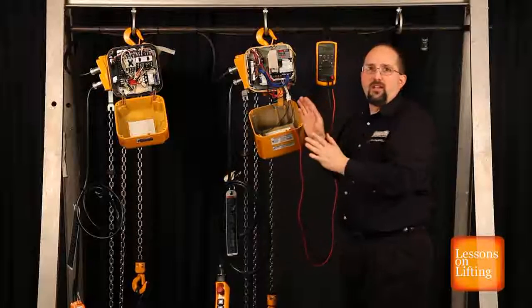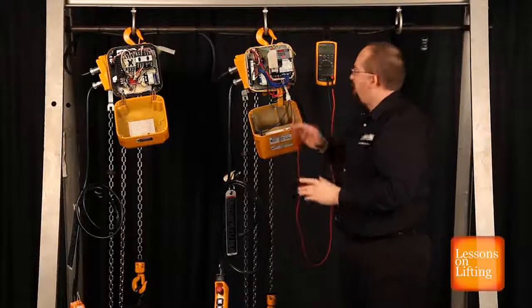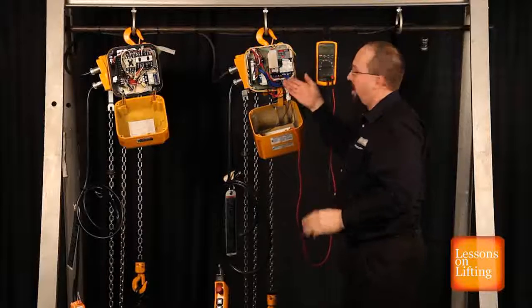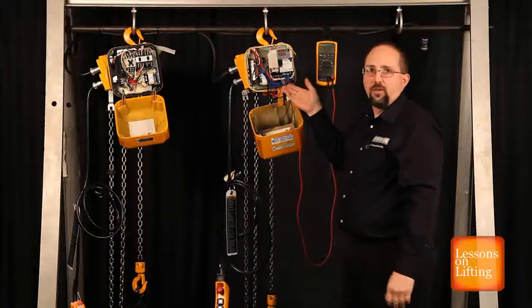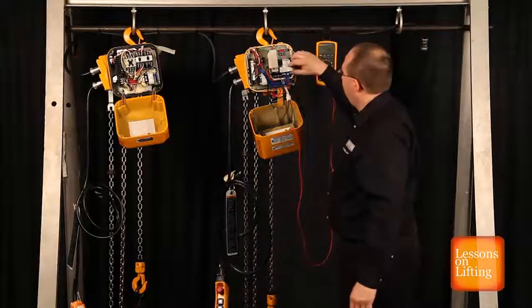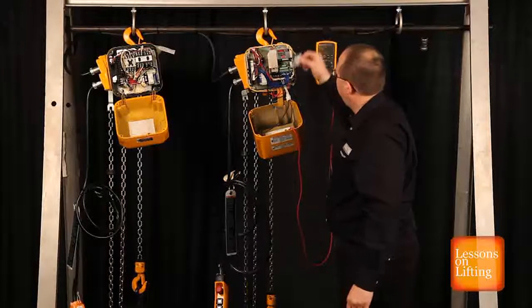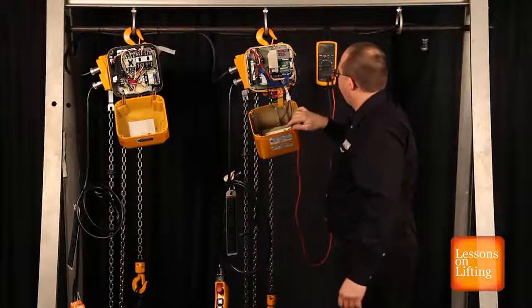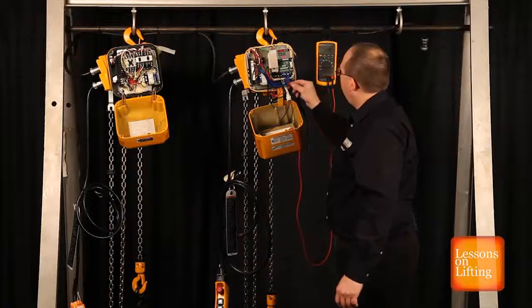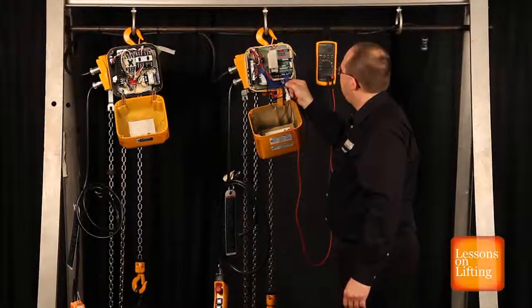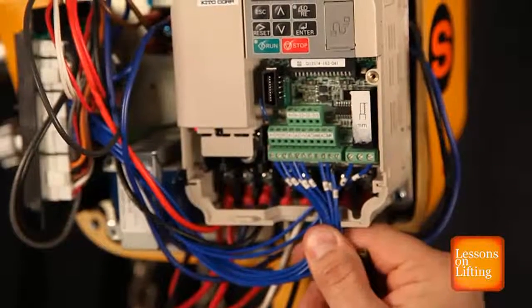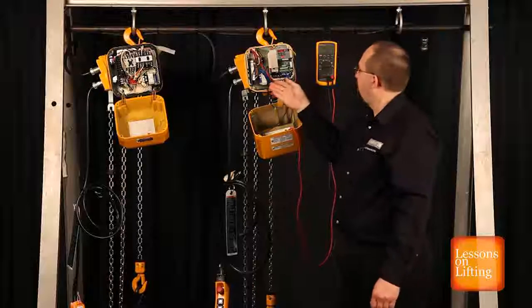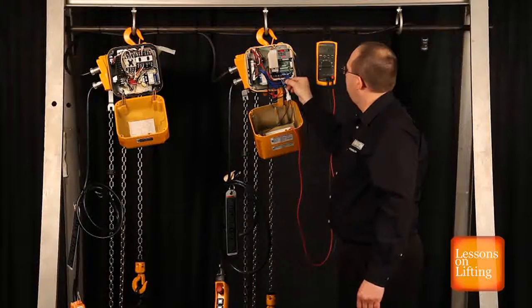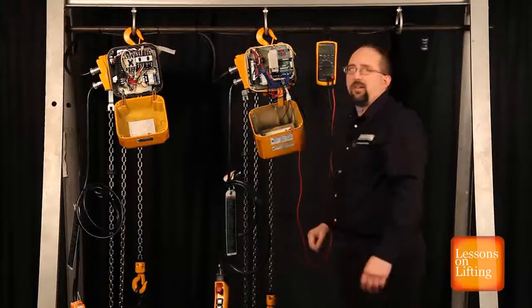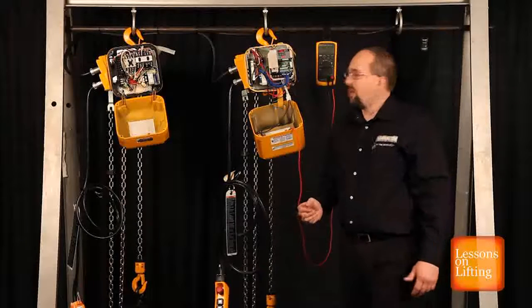Be aware the VFD is hot. Okay, the unit's plugged in. We do have 460 or 230 volts here, so be careful where you're poking around. Take that little sticker off. Want to make sure that our wires are tight here. HC and H1 are what's connected to the VFD. Everything looks good here. Starting to look like maybe we have a bad VFD.